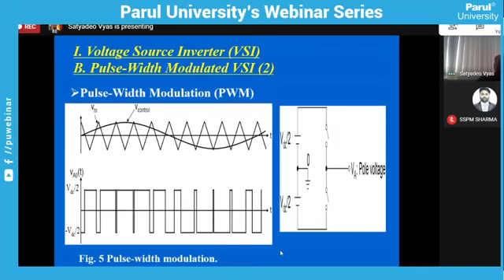In some applications, after reaching the base speed by controlling the frequency, we want to go beyond that point. Suppose a 1500 RPM motor, if I consider slip, say a 1460 RPM motor, I want to run it at 1600 RPM. How can I run it? I can run it with a VFD. From 0 to 50 hertz, we can run the motor with constant torque.